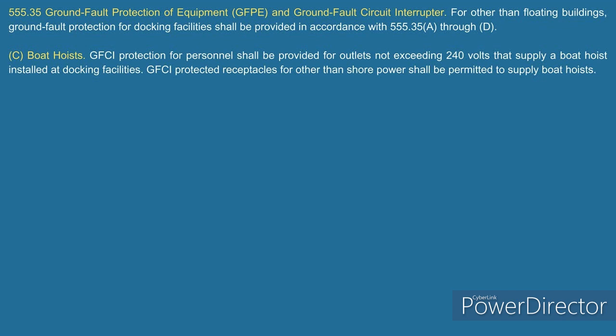That's right. And look at this, they even go a little further. They talk about boat hoists here. It says GFCI protection for personnel shall be provided for outlets not exceeding 240 volts that supply a boat hoist installed at docking facilities. And then it tells you GFCI protected receptacles for other than shore power shall be permitted to supply boat hoists. They're telling you it's a receptacle.